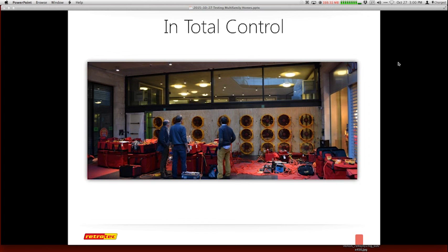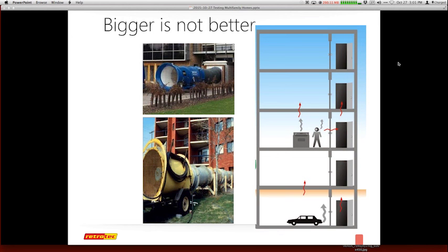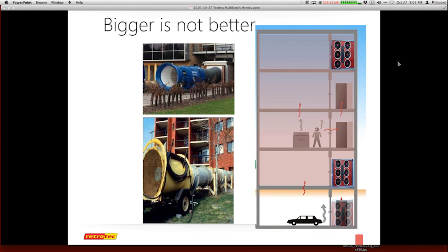So here's a 24-fan Passive House mall being tested in Europe, and it did pass. Larger is not always better. Some folks went with the super large mega fan, only to realize that they were not able to get the amount of pressure throughout the structure from one small opening. It may work great in an airplane hangar, but they found it was really a struggle to get that much air moving through the entire structure at one time.